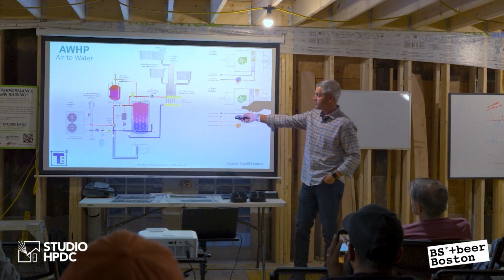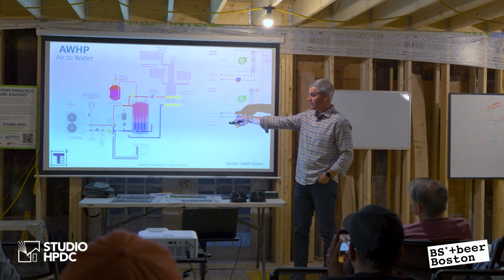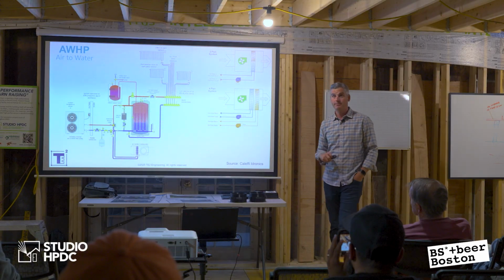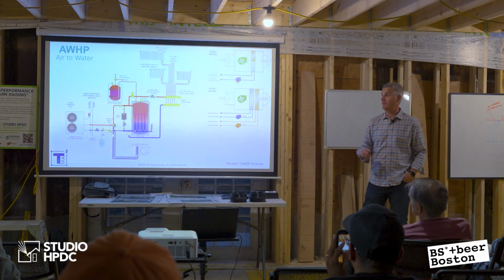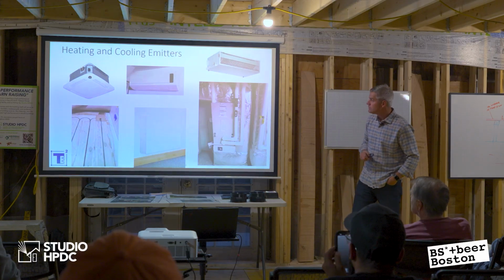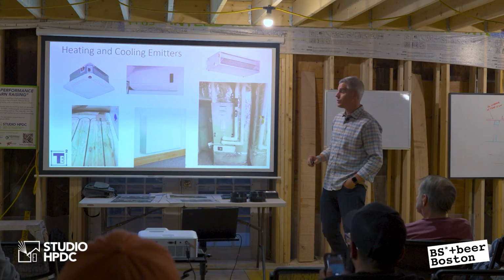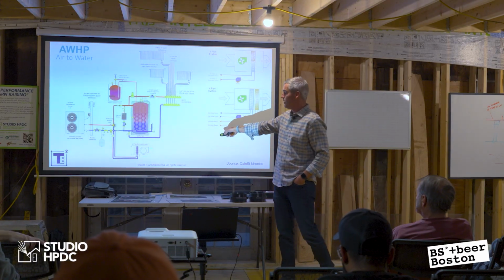So the system can heat this buffer tank up, then the diverting valve can flip and make chilled water, and it can send chilled water to that air handler. The chilled water can do cooling and dehumidification. You need another storage volume? You had one storage volume. Yeah, another one, which has 2 buffer tanks, one for cooling, one for heating.